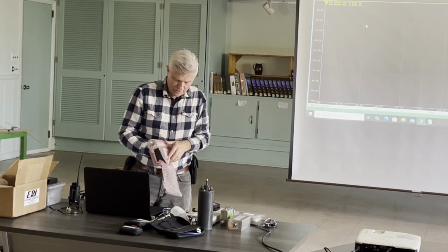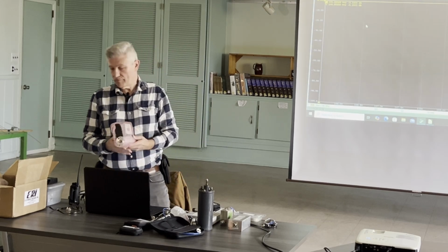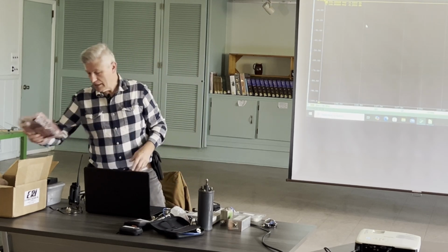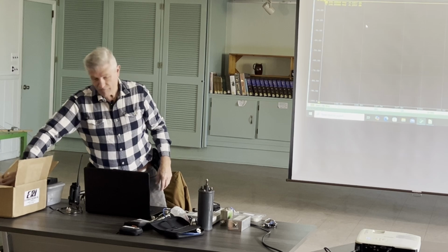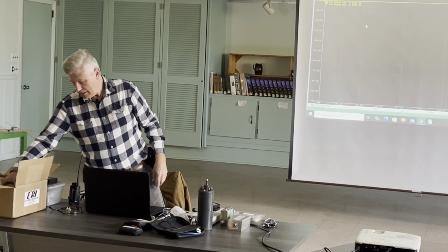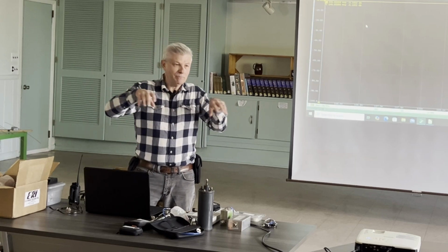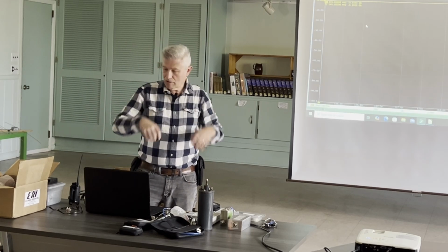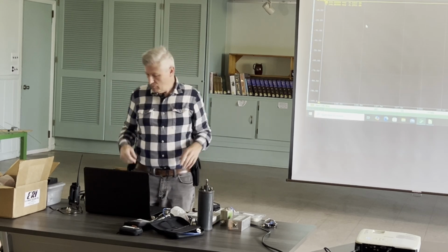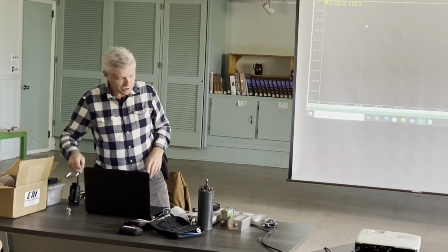This is an experimental thing, but 2.5 megawatts worth of RF power, and that's not effective radiated power. That's 2.5 megawatts of power that they needed to measure, and they put a pair of our meters on the same directional coupler. The line section had 2 directional couplers on it. They wanted to be able to compare the two to make sure they were within tolerance, and we met the spec, which was 1%.